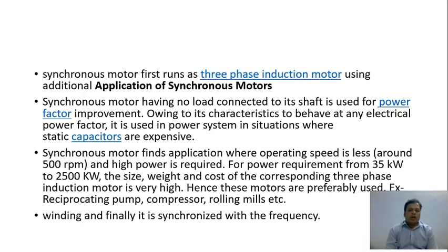A synchronous motor with no load connected to its shaft is used for power factor improvement. Owing to its characteristic to behave at a leading electrical power factor, it is used in power systems in situations where static capacitors are expensive. Synchronous motor finds application where operating speed is low, around 500 rpm, and high power is required.